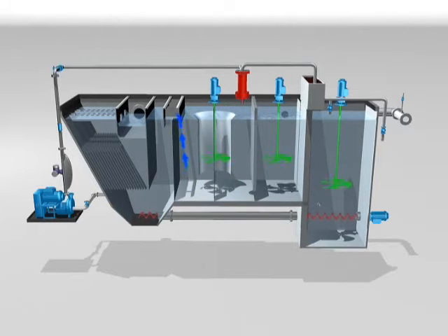The fully flocculated water then enters the settling tank via a siphoid baffle to avoid the transfer of turbulence from the agitated zone. The microsand ballasted flocks settle quickly to the bottom, whereas the clarified water rises through the lamella at a normal velocity of 80 meters per hour.